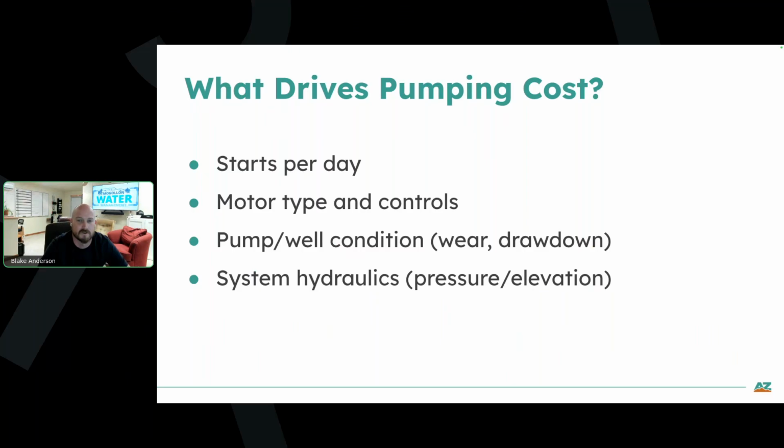And so then there's also your general condition of your motor and impeller, or even the well itself. So if your water level downhole is lower right now than it was 5 years ago, that means that you're going to have less head pressure coming into the inlets, which means that you're going to need more energy to lift that water than you did previously. There's also system hydraulics. So how much head are you pushing against?